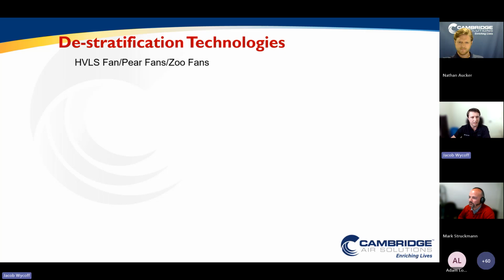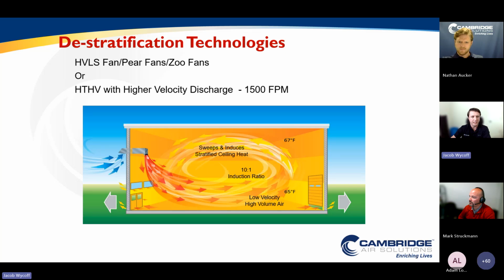Other technologies often consider things like HVLS fans, Pear fans, or zoo fans to get that heat from the ceiling down to the floor and to destratify that space. And this is great, but HTHV actually doesn't require that. HTHV uses a high velocity discharge, anywhere from 1,500 to 2,000 feet per minute, that's able to destratify and mix the air within these spaces. It's going to discharge the air at a 45-degree angle.